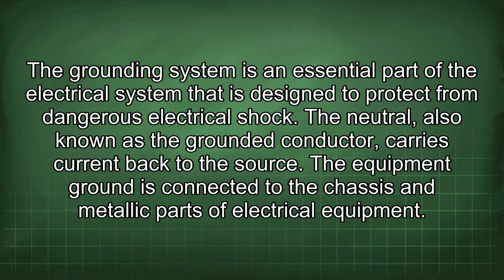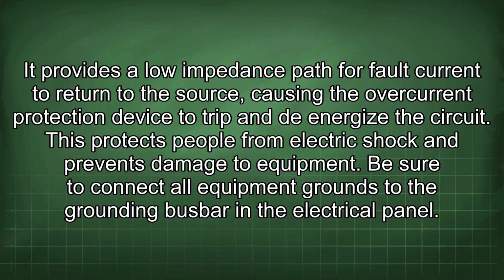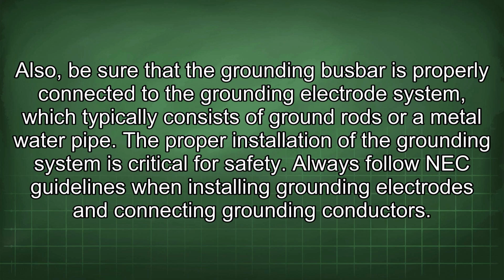The grounding system is an essential part of the electrical system that is designed to protect from dangerous electrical shock. The neutral, also known as the grounded conductor, carries current back to the source. The equipment ground is connected to the chassis and metallic parts of electrical equipment. It provides a low impedance path for fault current to return to the source, causing the overcurrent protection device to trip and de-energize the circuit. This protects people from electric shock and prevents damage to equipment. Be sure to connect all equipment grounds to the grounding busbar in the electrical panel. Also, be sure that the grounding busbar is properly connected to the grounding electrode system, which typically consists of ground rods or metal water pipe. The proper installation of the grounding system is critical for safety. Always follow NEC guidelines when installing grounding electrodes and connecting grounding conductors.